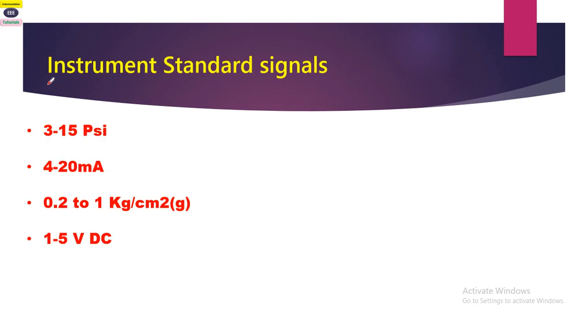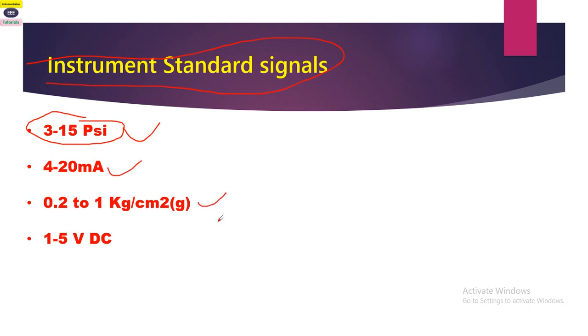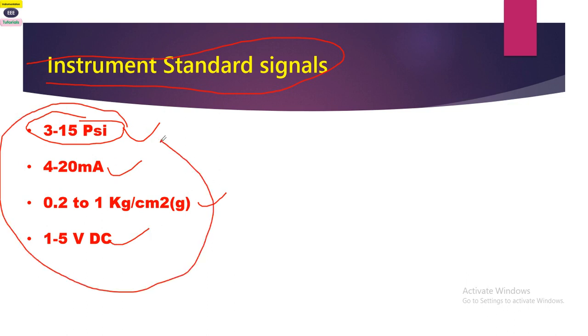Now, what are the instrument standard signals? There are four: 3 to 15 PSI, 4 to 20 milliampere, 0.2 to 1 kg per cm squared, and 1 to 5 volts DC. These are the four main instrument standard signals which can be used for measuring the process variable. If asked in an interview, you can simply list these four.